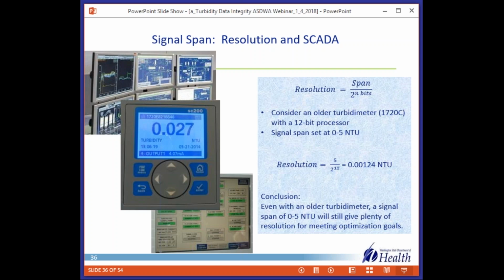So resolution is dependent on 2 things: the span that you set in the controller and the type of processor inside the turbidity sensor. So if you think about an older turbidimeter like a 1720C, and we did see a few of those in our project, it has a 12-bit processor, and we're talking about setting the signal span from 0 to 5. So you put those values into this equation, so 5 divided by 2 to the power of 12, and you can see that the resolution is 0.00124. So we're talking here the third digit.